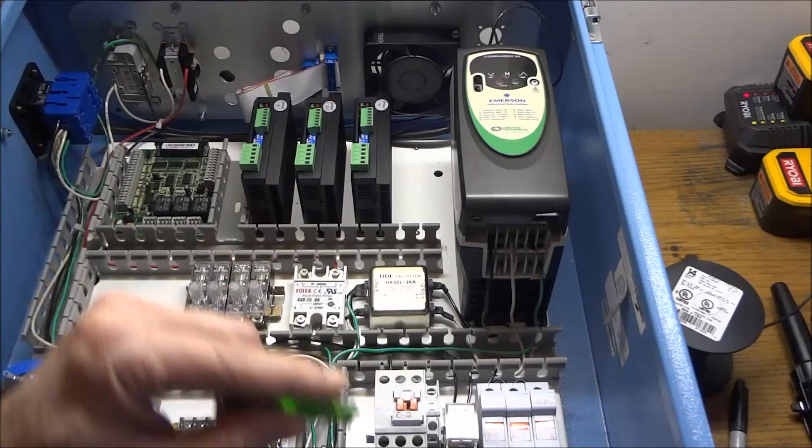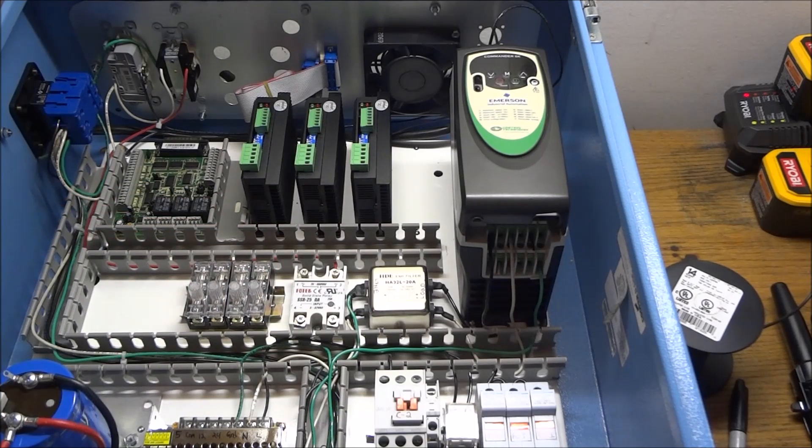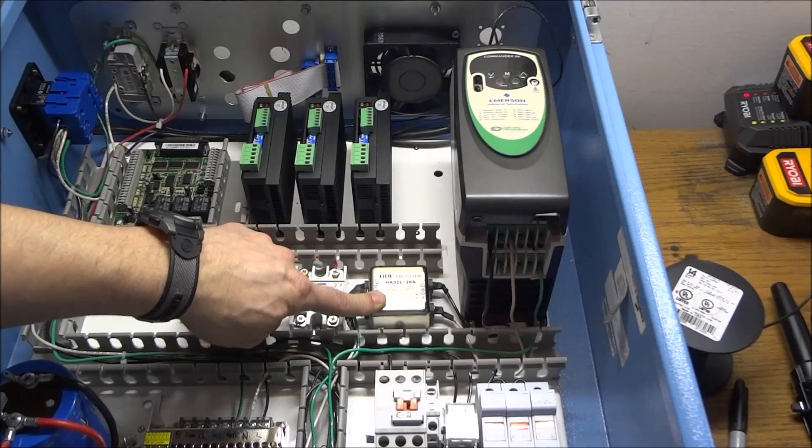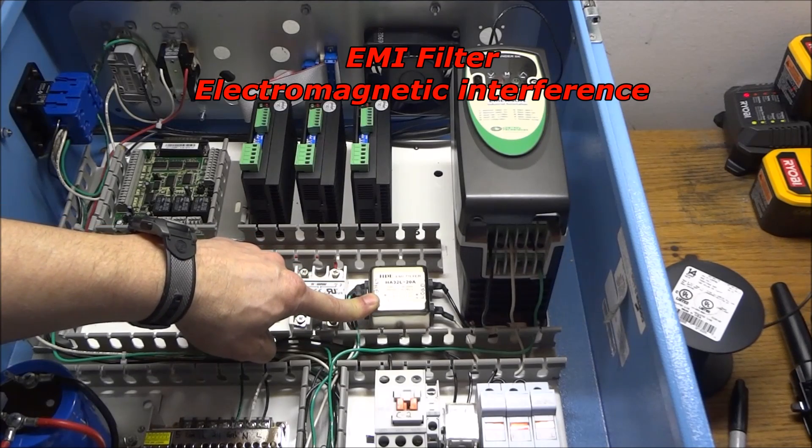VFDs will generate electromagnetic interference. And when they do, what happens is this interference goes out to the motor, comes back through the ground circuit, and tries to find the source of the interference which is your VFD. And what happens is that bleeds upstream to all the other components in the system and it can cause you problems. So if you've got a VFD, pick yourself up one of these EMI filters.